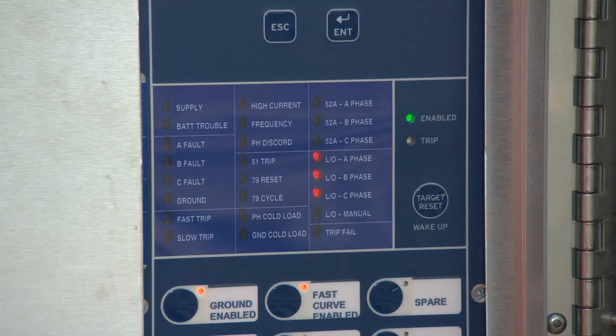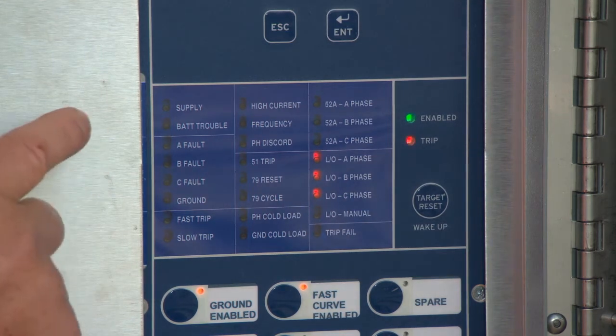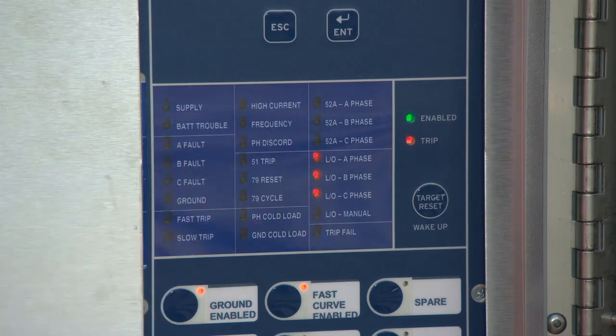Below this is the frequency fault indicator LED. This is not programmed into the control. Phase discordance is not programmed into the control. Were this to trip on phase discordance, the LED would become red. Next is the 51 trip sequence indicator LED. This will illuminate red as the recloser cycles through its tripping sequences.